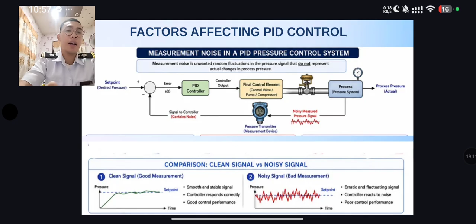The derivative is the most important in measurement noise because it is highly sensitive to noise. The derivative term calculates the slope of the error. High frequency noise has incredibly steep slopes, even if the amplitude is tiny. Feeding a noisy pressure signal into the derivative term will result in erratic spikes in the control output. This can cause severe valve chatter, which will rapidly destroy the mechanical packing and stem of the control valve.